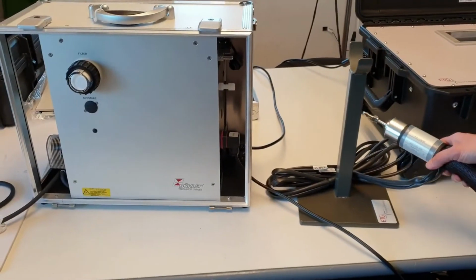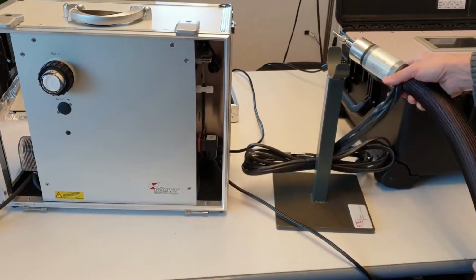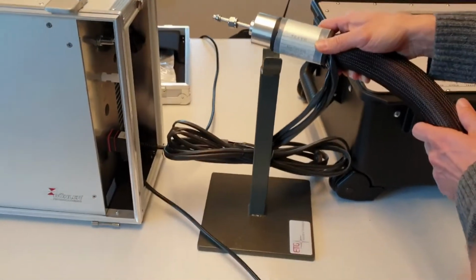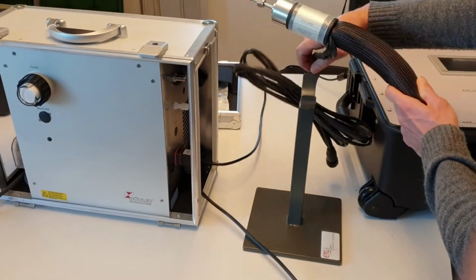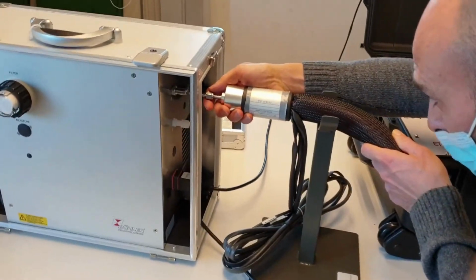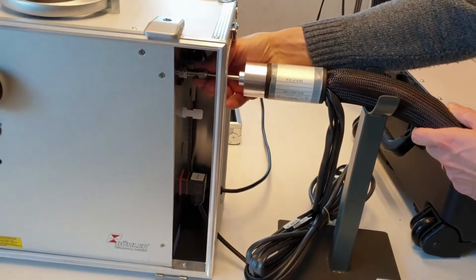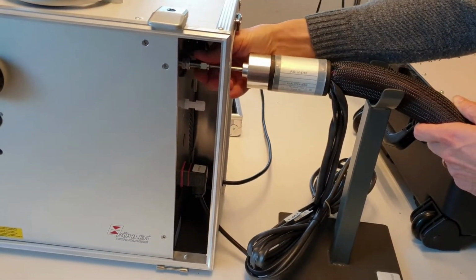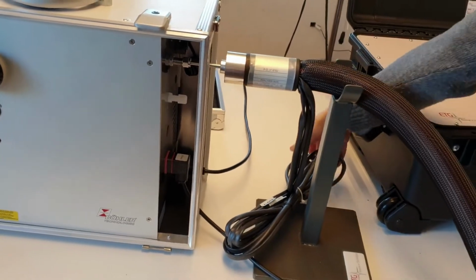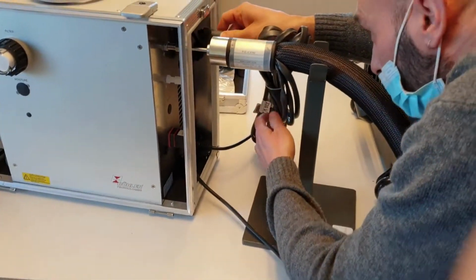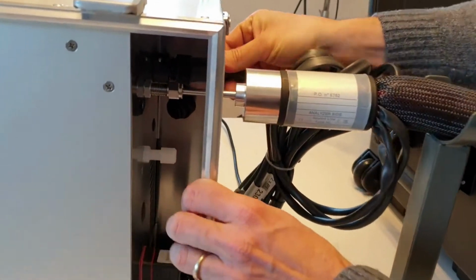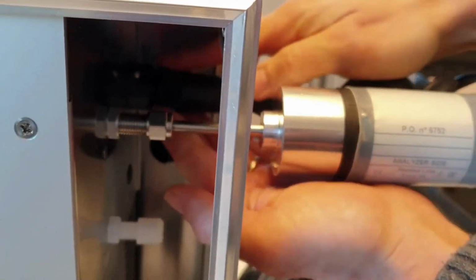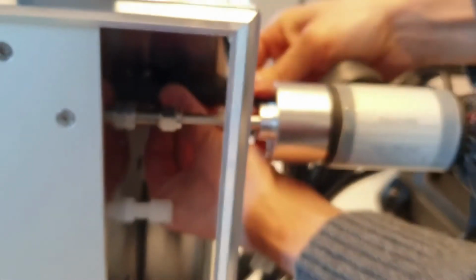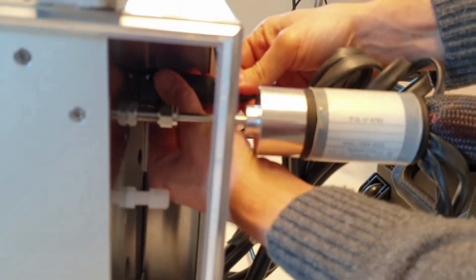Then the heated line has to be also connected to the sample conditioning unit, pneumatically on the sample inlet, and electrically on the power supply heated line. There is only one way to connect. It's not possible to make a mistake.